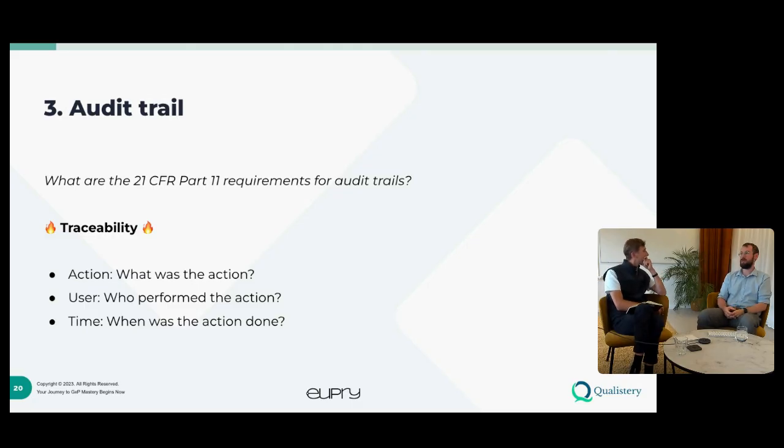Part 11 does not specifically require you to do a review of the audit trail. As I remember, it has some terminology regarding making sure that logs are verified in some way, but I must be sure there. But I often think that on a risk-based approach, going through the audit trail when reviewing your system anyway would allow you to make sure that no one did an unauthorized or accidental change to an alarm setting, as an example.